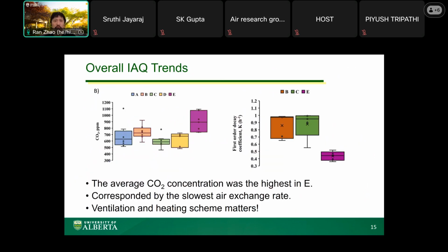Starting with overall indoor air quality trends, the diagram on the left shows the campaign's overall averaged CO2 concentration in the 5 buildings, A to E, that we measured. For 4 of the buildings, A to D, the median CO2 concentration is about 600 to a little above 700 ppm. Given that outdoor background CO2 is 420 ppm, 600 to 700 ppm indoors in Canadian buildings is pretty typical, due to air tightness. But building E, shown in purple, had a particularly high CO2 concentration at 900 ppm—a little high even for a Canadian indoor environment. So we decided to investigate further into the potential reason for that.